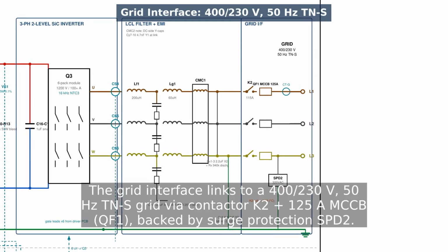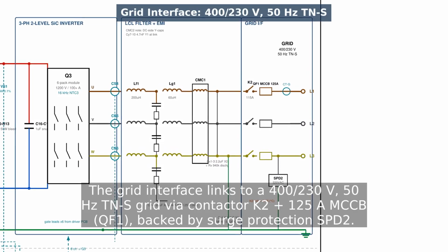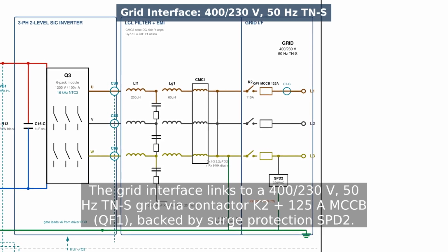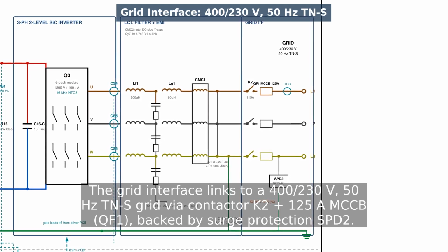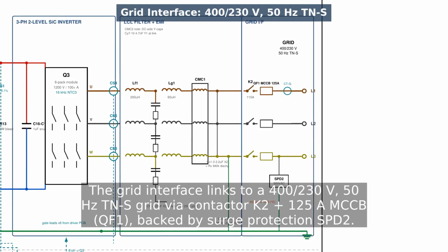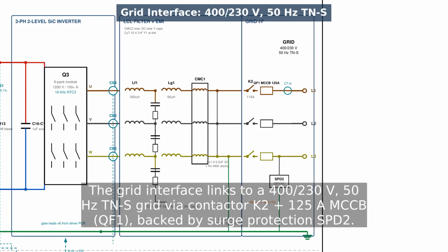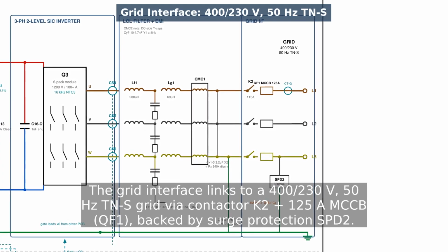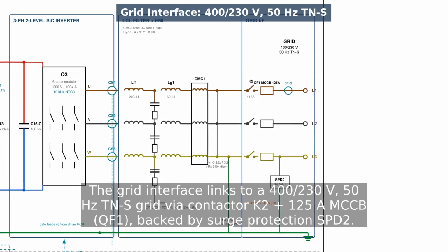Finally, the grid interface links to the 400/230 volt, 50 Hz TN-S utility grid via contactor K2 and a 125 amp MCCB breaker, backed by AC surge protection SPD2.